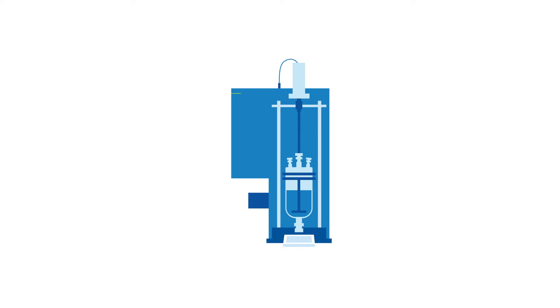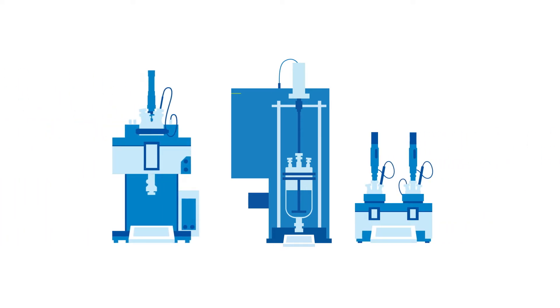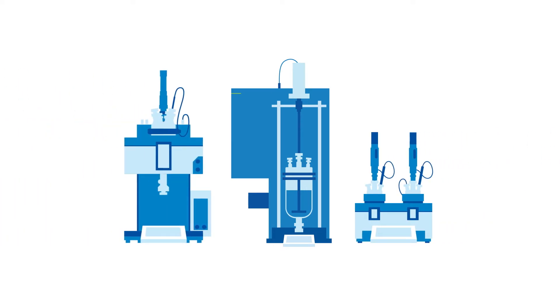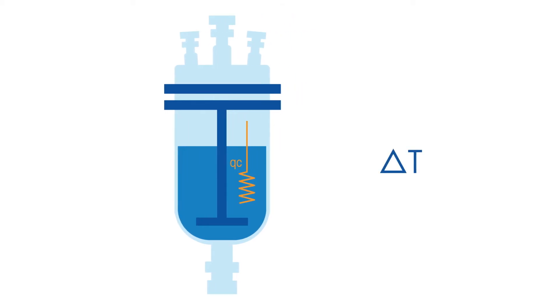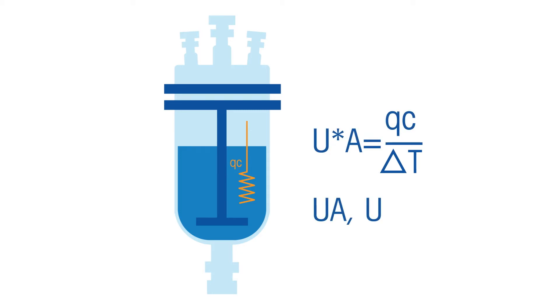To determine the conversion factor U times A, the Mettler Toledo reaction calorimeters RC1mx, EasyMax HFCal, and OptiMax HFCal use a small electrical heater that introduces a certain amount of heat into the system under isothermal conditions. Subsequently, the response of the system is measured, which then allows the conversion factor and the overall heat transfer coefficient to be calculated.